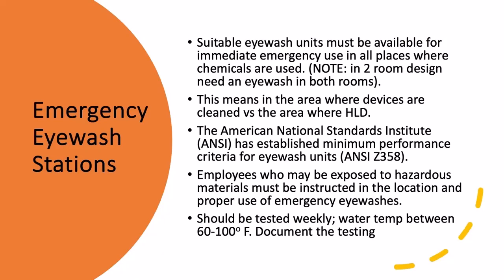Emergency eye wash stations. You need an eye wash station in all places where chemicals are used. So in a 2-room design, you will need an eye wash in both rooms. This means in the area where devices are cleaned versus the area where they're high-level disinfected.